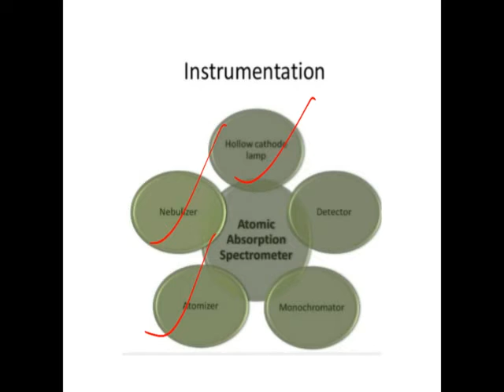The transmitted radiation passes through a lens and the monochromator, and finally it is detected by the photomultiplier with the help of a digital display or a computer. So this transmitted intensity is measured, and it is the characteristic of a particular metal. So that is the simple working of atomic absorption spectroscopy. This instrumentation consists of a hollow cathode lamp, then nebulizer, atomizer, monochromator, and finally the detector.